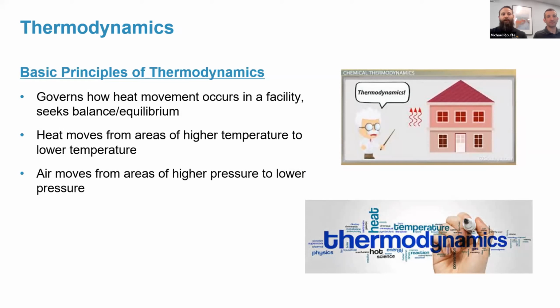It's also important to note that air is going to move from a high pressure area to a lower pressure area. So if a building is positively pressurized within, it's going to be pushing all that conditioned air outside. On the other hand, if there's a negative pressure inside the building, it's going to be pulling in unconditioned outdoor air through cracks in the building and portions of the envelope where it shouldn't be.